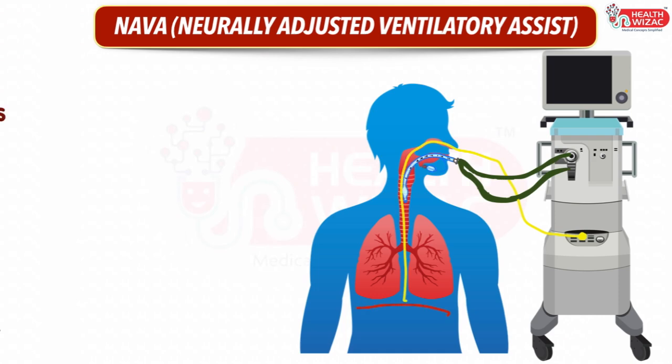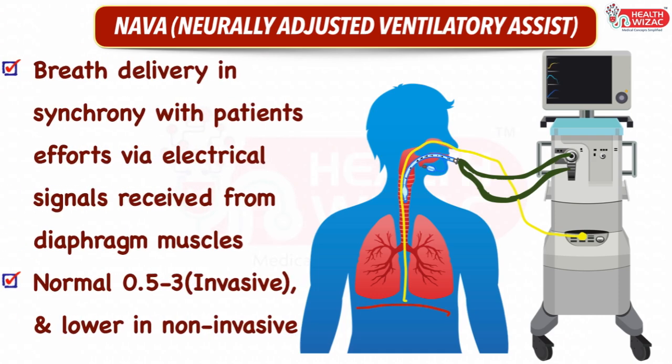Next is NAVA, or Neurally Adjusted Ventilatory Assist mode. It is an assist mode of ventilation in which the ventilator delivers breaths in synchrony with the patient's efforts via electrical signals received from the diaphragm. Normal NAVA level ranges between 0.5 to 3 for invasive mode and is lower in non-invasive mode.